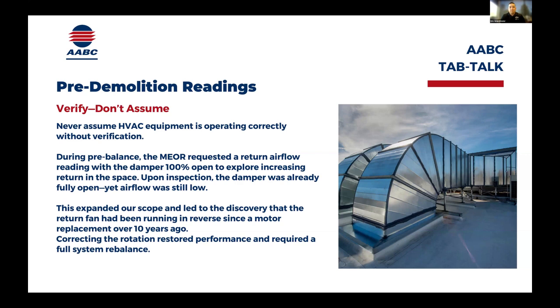Once we got to the air handler, we realized that the fan had been operating backwards for over 10 years. They replaced the motor. They didn't do the polarity right, and the motor had been operating backwards for over 10 years. So of course that expanded our scope into finding this issue, having to reverse polarity, and then going back and rebalancing the return system. So interesting, don't assume that everything is just operating correctly, go and verify for yourself.